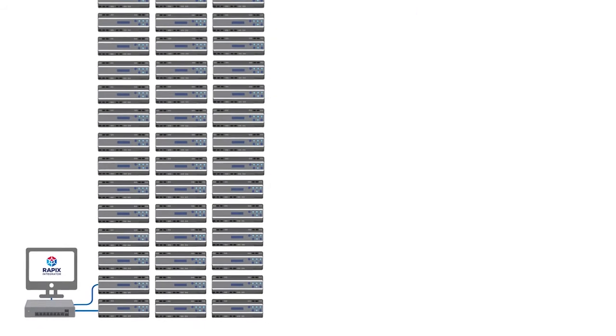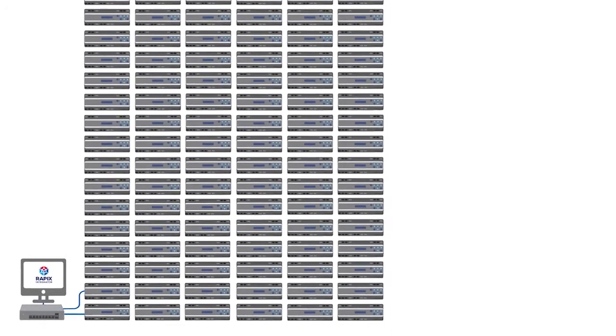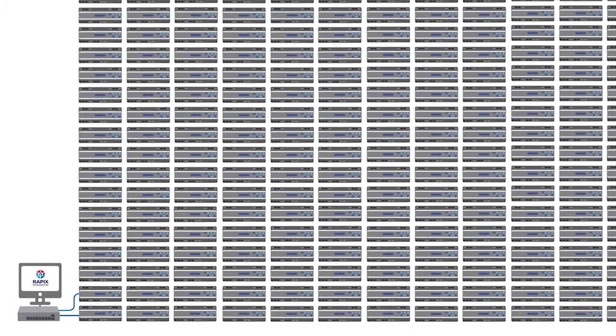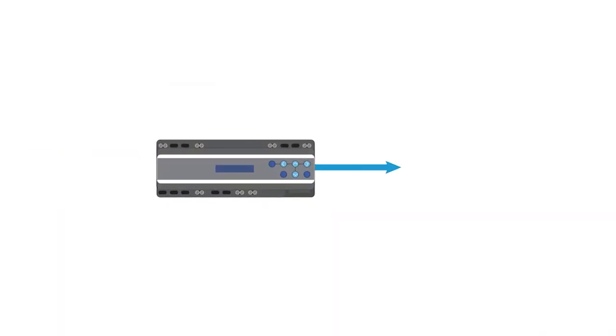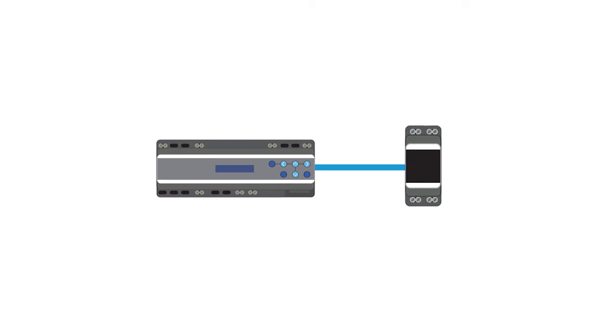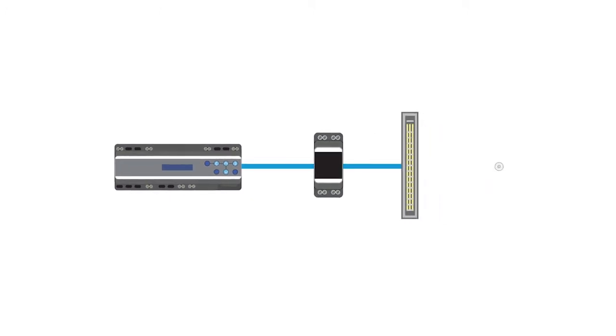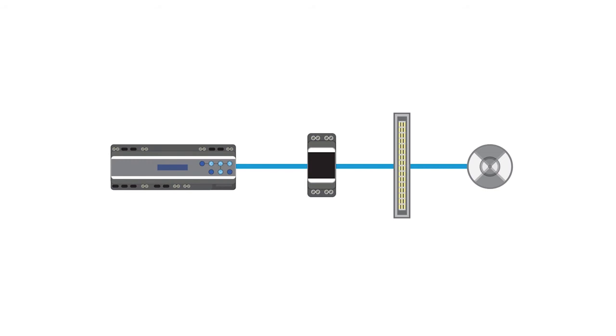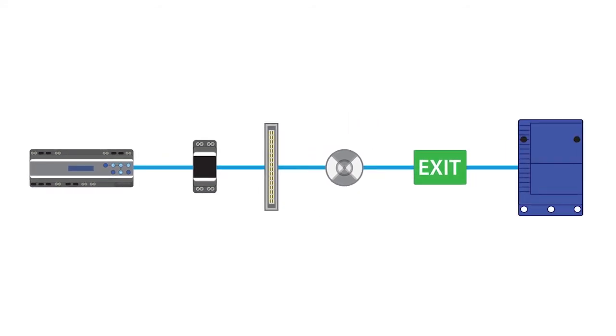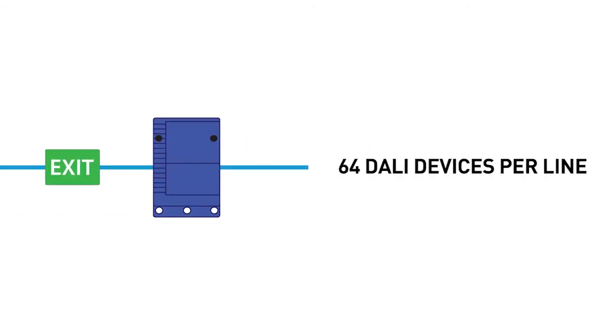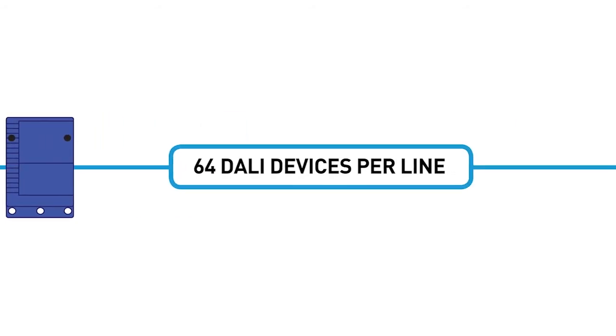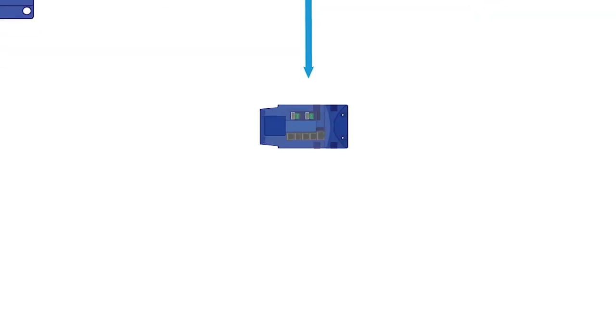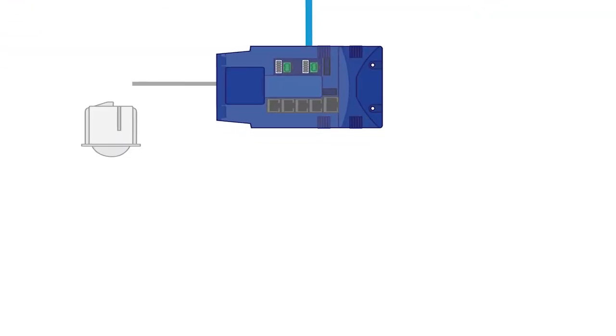Like any DALI compliant system, each DALI line requires a DALI power supply unit. DALI luminaires, emergency luminaires, and exit signs are connected to each DALI line, along with other DALI compliant devices such as DALI relays. Up to 64 DALI devices can be connected to each DALI line.